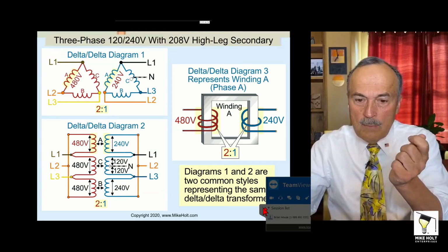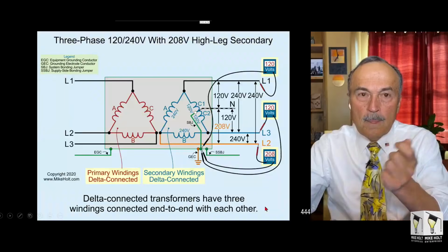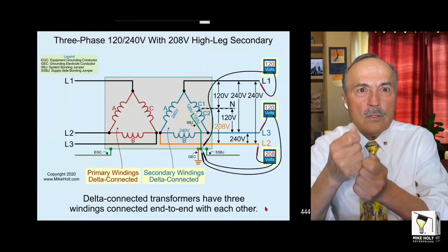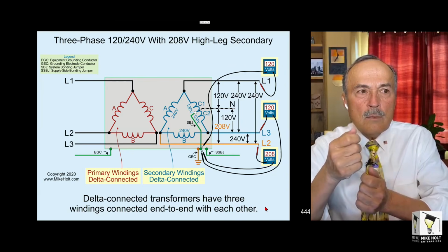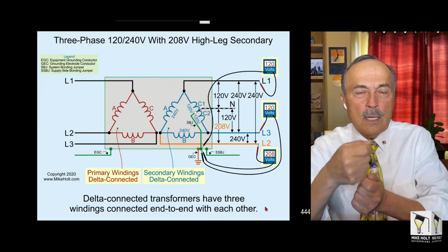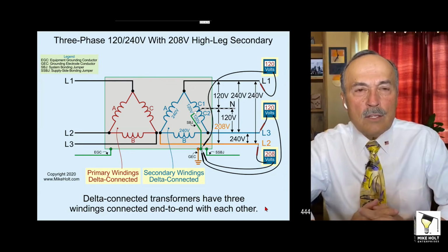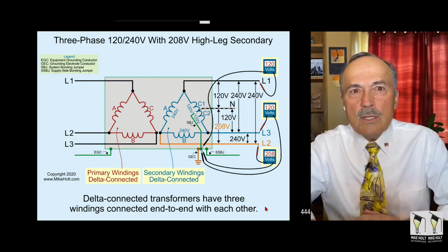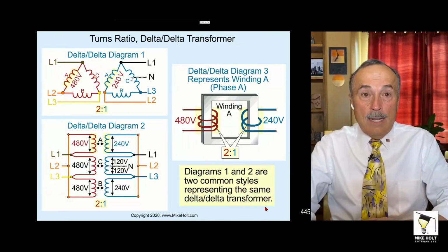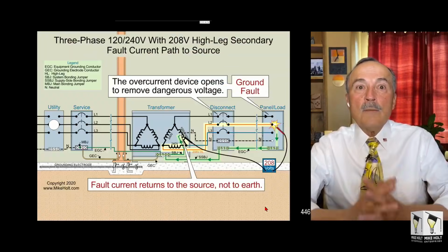Okay. What about line 1 to line 2? I'm sorry, let me get back here. Well, line 1 to line 2 and a high leg is 240. Line 1 to line 3 is 240, and line 2 to line... So you can figure out what kind of transformer, if you didn't have a label on there, is what are you getting in there? All right, now, what about a fault?